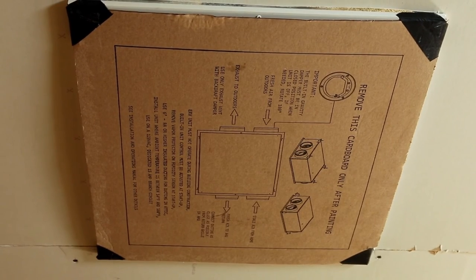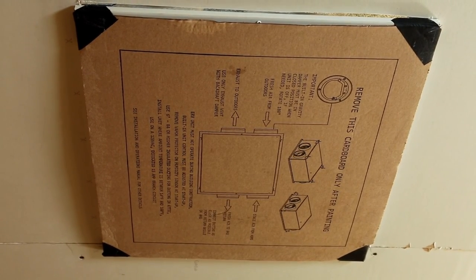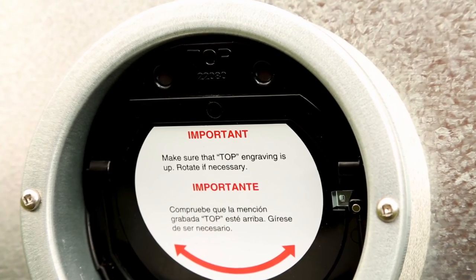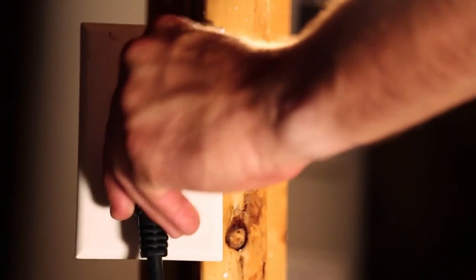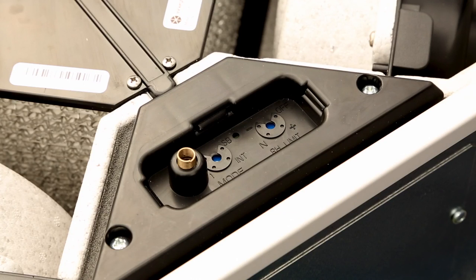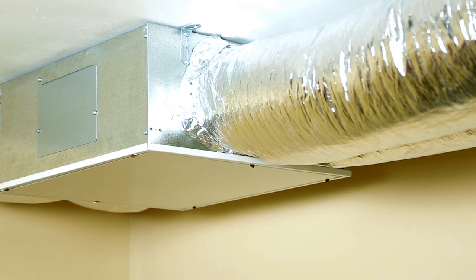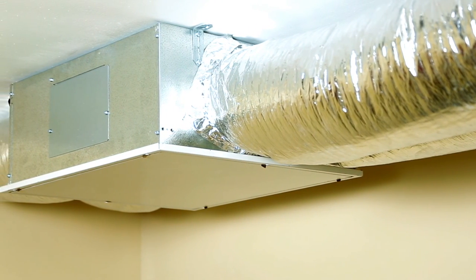Before starting the unit, remove the protective cardboard from the door if you haven't already and verify the damper orientation. When the unit is powered on, it will go through a booting sequence. If there's a problem, the LED light will blink. Fast blinking indicates a motor problem. Slow blinking indicates a problem with the RH or temperature sensor. The ERVS-100 is now installed and ready for use.